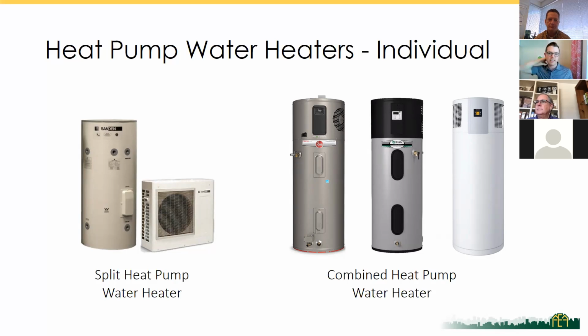The one on the left is a split type heat pump water heater, where you have the tank and the heat pump. One thing I really want to emphasize with this type, and really any heat pump water heater you see with a box and a tank, is that all of the refrigerant is inside that box, period. It's factory sealed, done. The only thing connecting the box to the tank is water pipes. So you can just think of it like a little electric boiler that does it very efficiently with refrigerant. There's no running of refrigerant lines or anything like that—all the refrigerant is contained within the unit. So that's a split type.